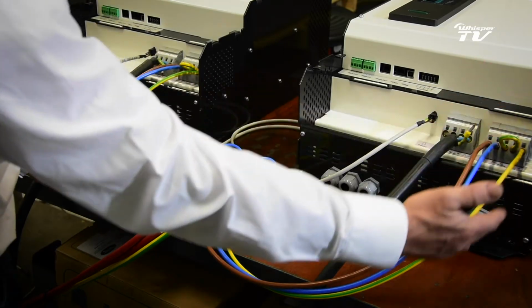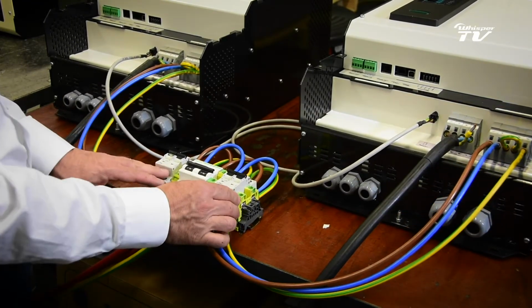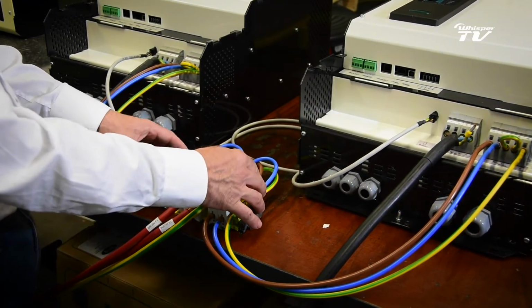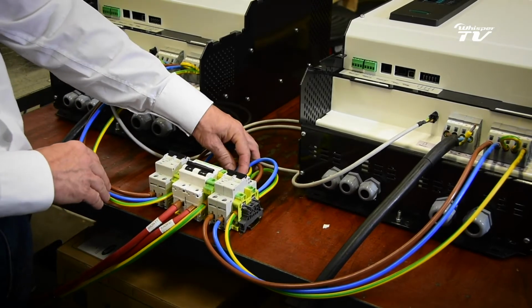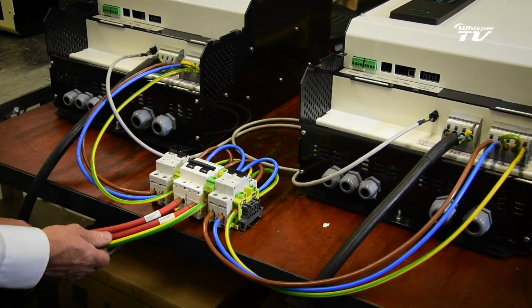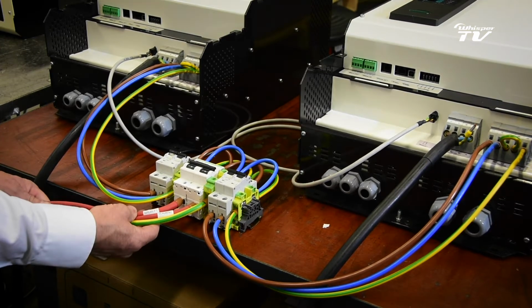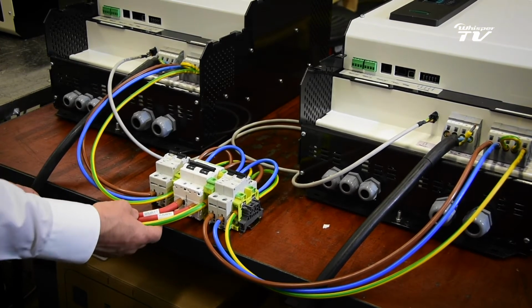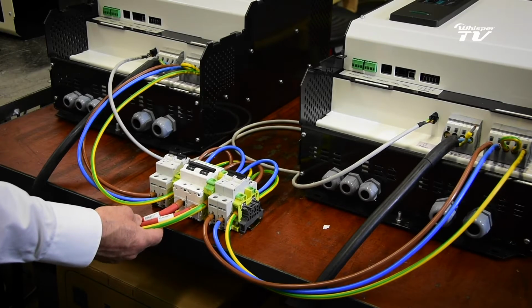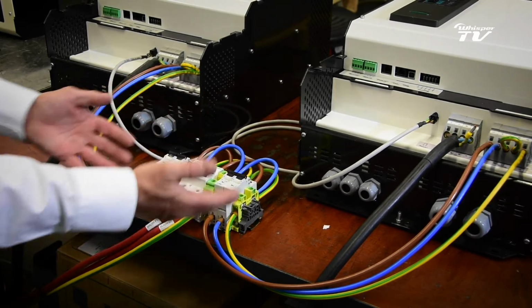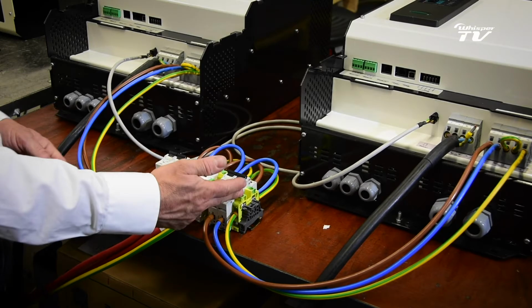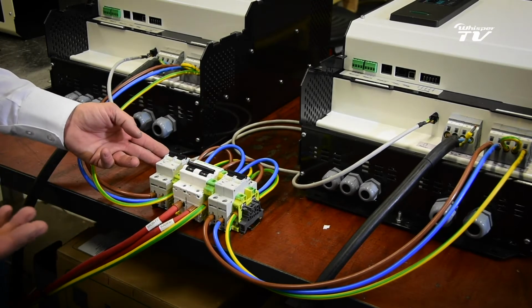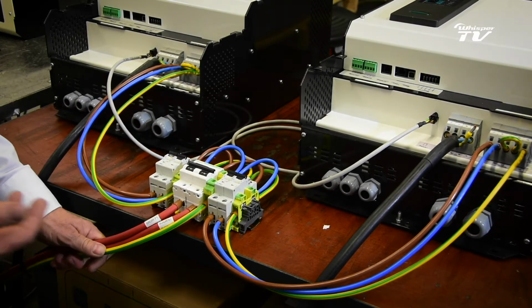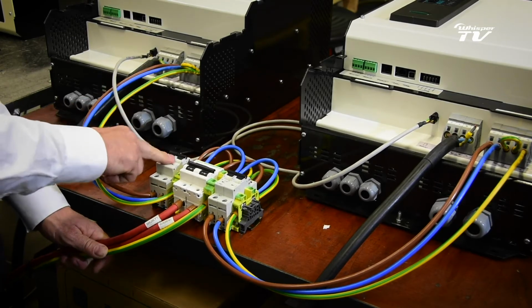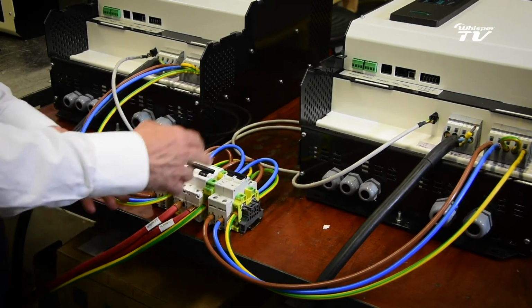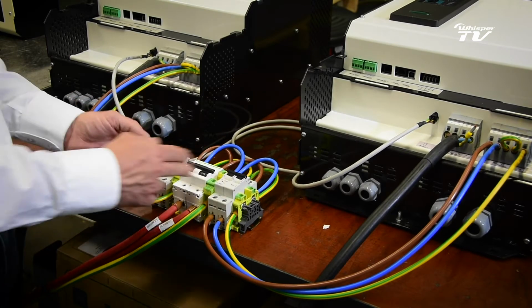The other inverter is exactly the same wired up. So we have 2 times 50 amp breaker going to the outside, connected into a 125 amp breaker, and these are the AC cabling to the ship or to the electrical system, which is in this case 30 kVA maximum. By doing this setup, we can blow either fuse, we can trip. So if we have a shorting in the ship and we have one generator running, for example this one, we can blow this fuse, and if we have 2 systems and we go over it, then we can blow either one if that's needed.